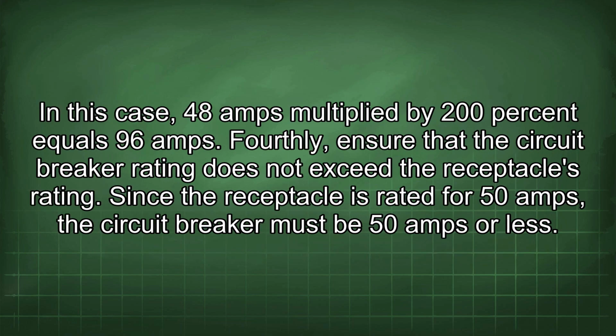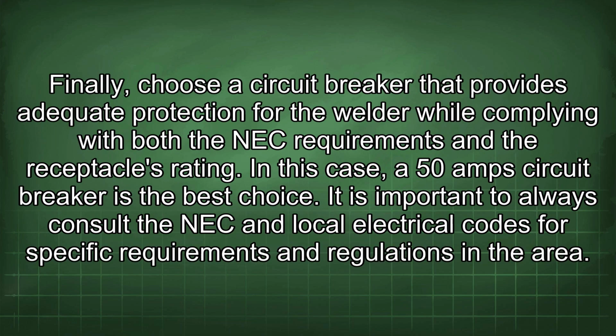In this case, 48 amps multiplied by 200% equals 96 amps. Fourthly, ensure that the circuit breaker rating does not exceed the receptacle's rating. Since the receptacle is rated for 50 amps, the circuit breaker must be 50 amps or less. Finally, choose a circuit breaker that provides adequate protection for the welder while complying with both the NEC requirements and the receptacle's rating. In this case, a 50 amp circuit breaker is the best choice.